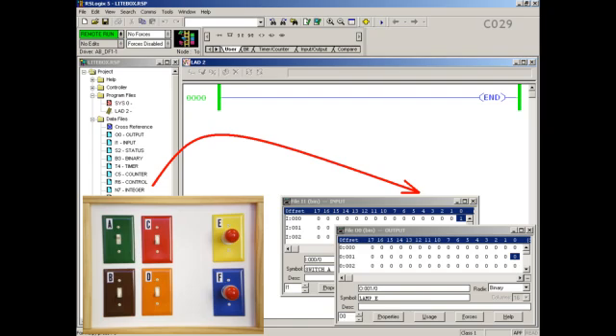So, when we turn switch A on and off in the field, the bit for switch A located in our PLC processor changes from a 1 to a 0. And when we manually change the 1 and 0 status of our bit for lamp E, the lamp out in the field actually turns on and off. Believe it or not, this simple exercise surprises quite a few experienced students, because they've always thought that nothing can happen inside the PLC until they write a program to tell the processor what to do. That's not true.